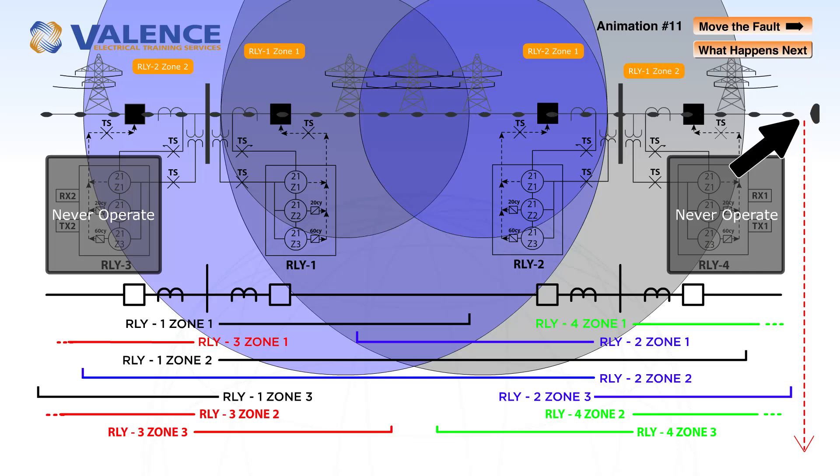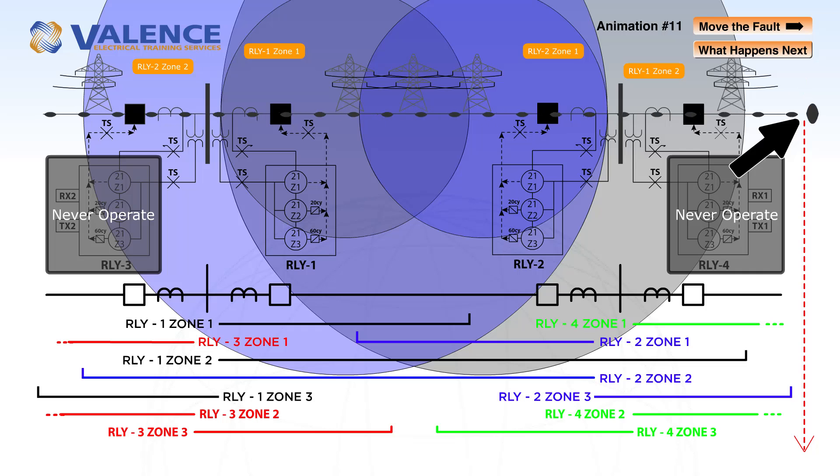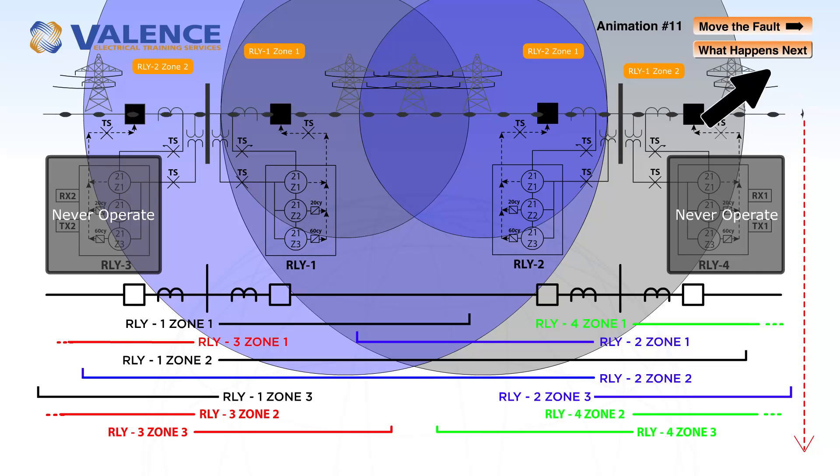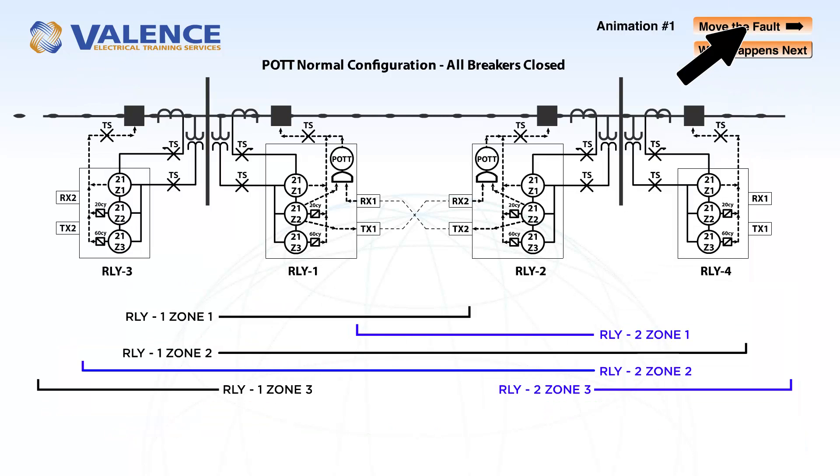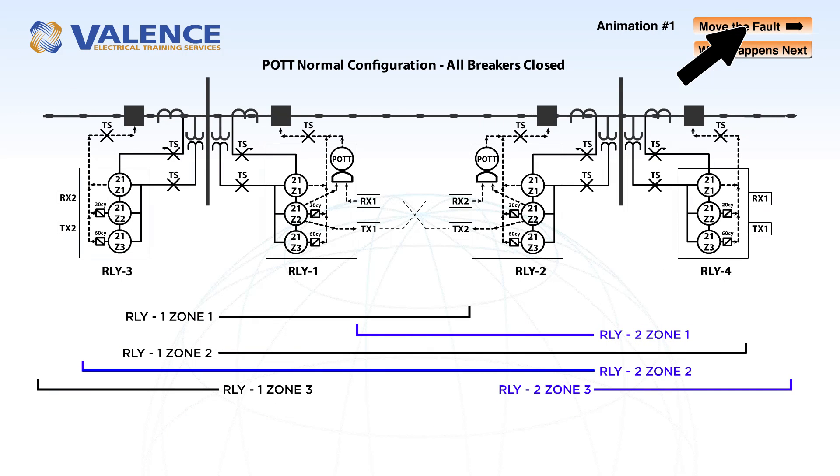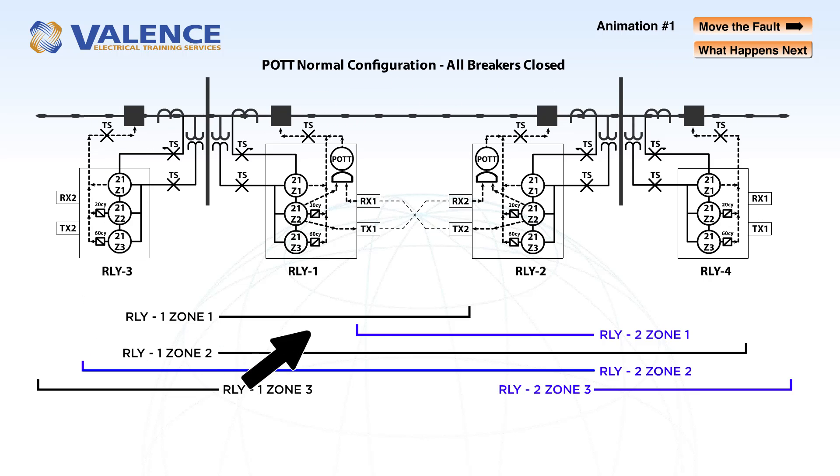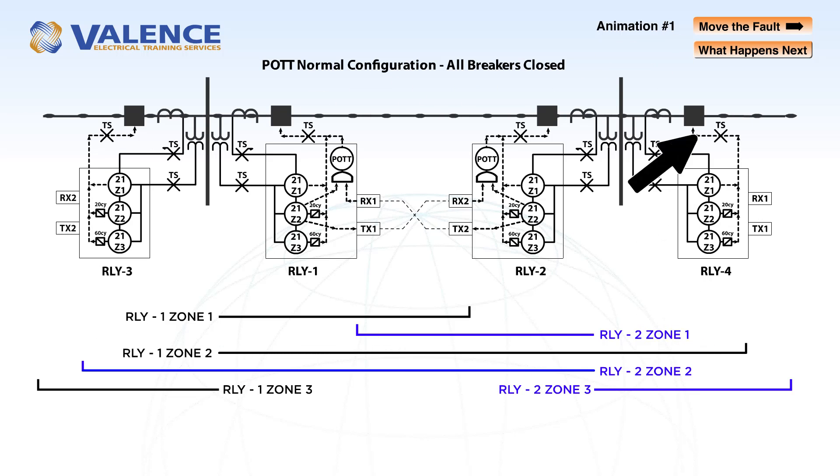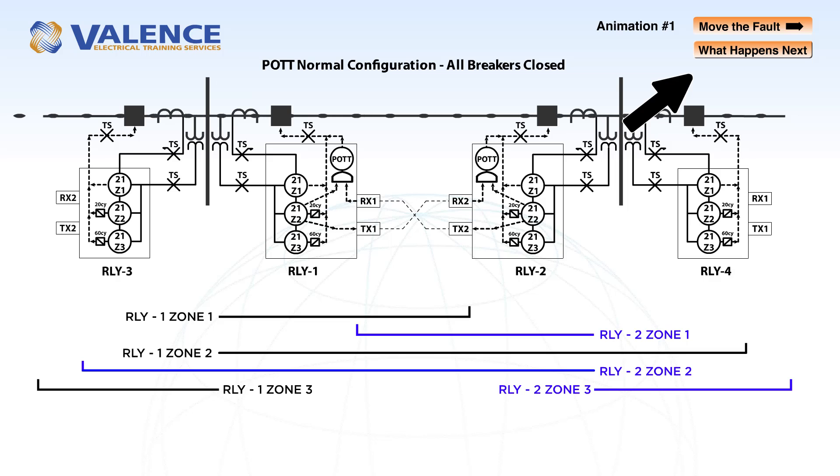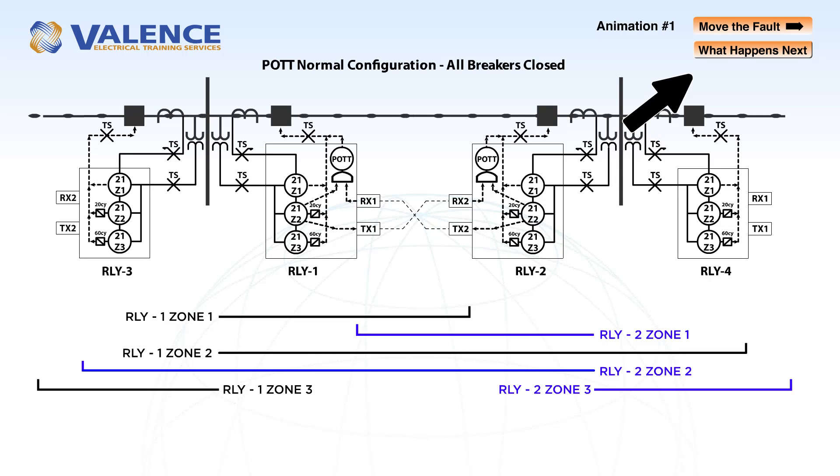Now that we know what will happen with normal line distance protection with no communication, let's see what happens when we apply a communication scheme. This drawing depicts a POTT, or permissive overreaching transfer trip scheme, which is the most common kind of communication assisted protection scheme that there is.